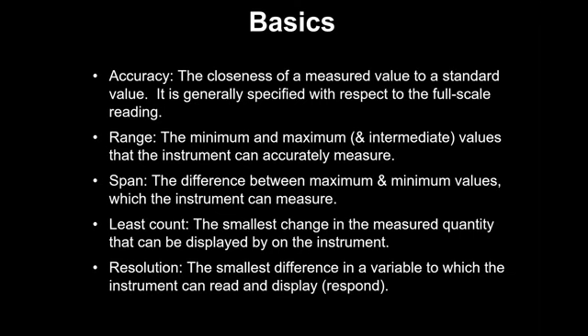So while selecting the instrument, the first thing we need to look at is the accuracy of the instrument. Accuracy is defined in two ways. Normally when we buy an instrument, they say this has 0.25% accuracy. But many times the manufacturer fails to say that it is a percentage of full scale reading. Full scale reading means the full span of that instrument, and not our reading. Some sophisticated instruments will say plus minus 1% of the reading, or they'll say both, plus minus 0.1% of the reading or plus minus 0.25% of the FSD, whichever is higher or lower.